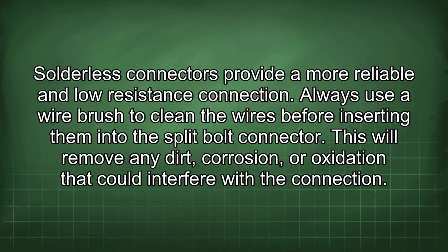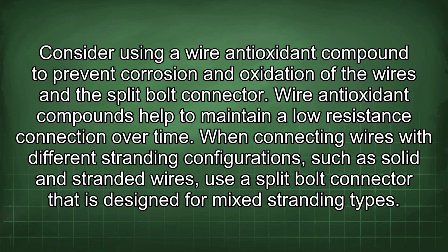Solderless connectors provide a more reliable and low resistance connection. Always use a wire brush to clean the wires before inserting them into the split bolt connector. This will remove any dirt, corrosion, or oxidation that could interfere with the connection. Consider using a wire antioxidant compound to prevent corrosion and oxidation of the wires in the split bolt connector. Wire antioxidant compounds help to maintain a low resistance connection over time.